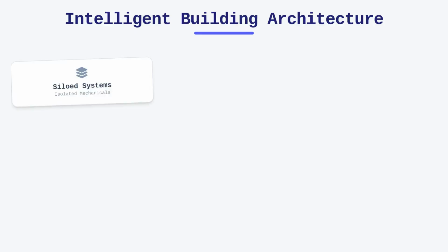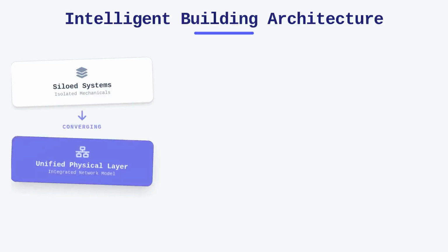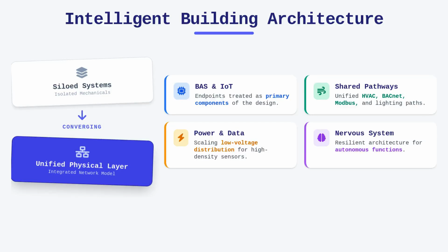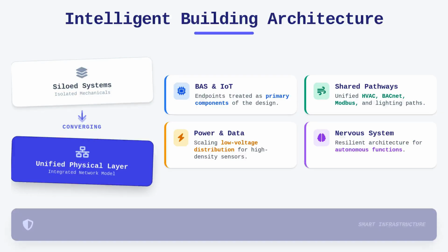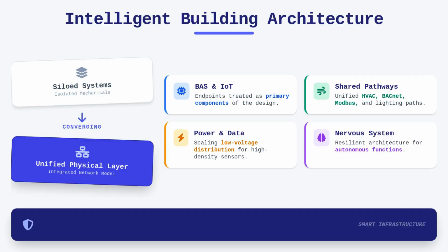We are moving away from siloed mechanical systems toward a converged network model, where HVAC controllers, BACnet protocols, Modbus arrays, and lighting control systems share the same pathway infrastructure as traditional data networks. This integration forces a reevaluation of how we manage low-voltage power and data distribution across thousands of ceiling-mounted sensors and occupancy monitors. When we incorporate devices like temperature and humidity sensors, we are essentially building the nervous system of the structure. The challenge lies in designing a resilient physical layer that can accommodate these high-density requirements without compromising the performance of the standard telecommunications backbone.